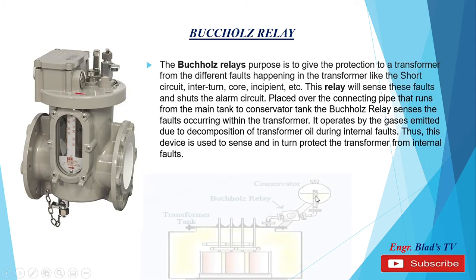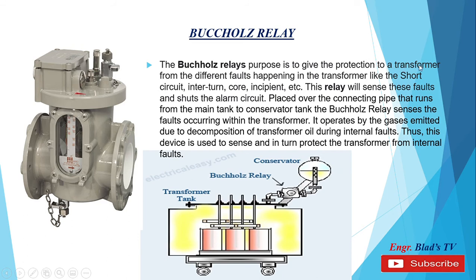Buchholz Relay. The Buchholz relay's purpose is to provide protection to a transformer from different faults happening in the transformer, like short circuit, inter-turn, core, incipient faults, etc. This relay will sense these faults and shuts the alarm circuit. It is placed over the connecting pipe that runs from the main tank to the conservator tank. The Buchholz relay senses faults occurring within the transformer and operates by the gases emitted due to the decomposition of transformer oil during internal faults. Thus, this device is used to sense and protect the transformer from internal faults. In this picture we can see the location of the Buchholz relay, which is connected between the conservator and the transformer tank through a pipeline.